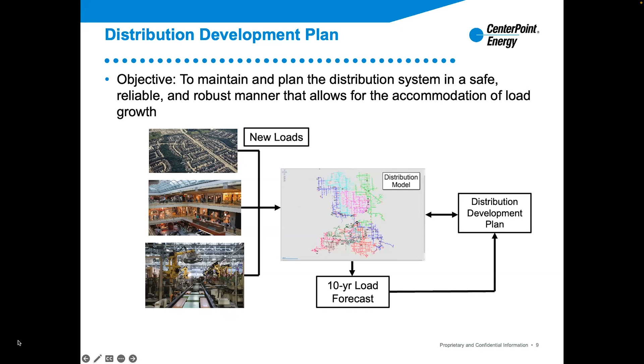Any customer that connects to our grid, we need to make sure they meet all these standards. They're not just connecting to us, we're connecting to them also. So we need to make sure they don't cause motor start flicker, they don't cause harmonic issues in the area. Their distributed generator doesn't cause any over voltage or back energize any faulted equipment. They can ride through voltage sags, and any automated rollovers or load transfers can be safely handled by the adjacent circuits.